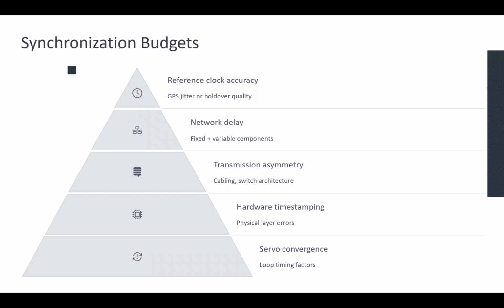On the next step, the system must consider jitter and holdover behavior for the local oscillator. We know that jitter introduces short-term variability into the timing signals. On the other hand, the holdover reflects how well a local clock maintains accuracy during an outage of the reference clock. So this drift that we're talking about must be estimated and included in the synchronization error margin. This is very important, especially for systems where continuous access to the reference clock is not guaranteed.